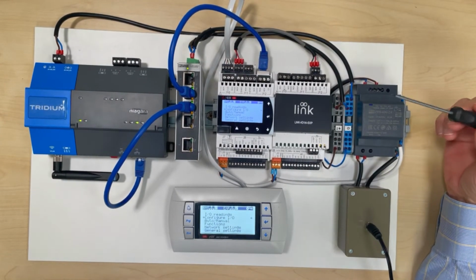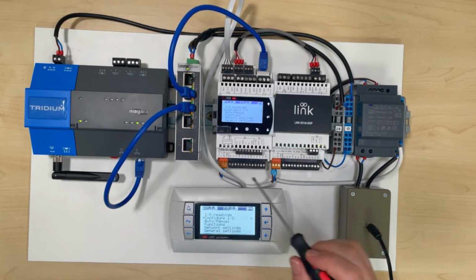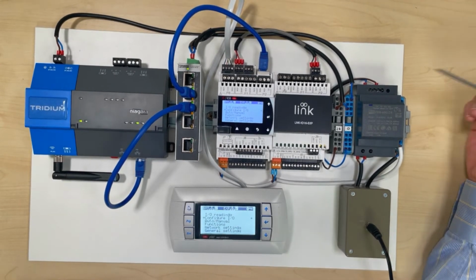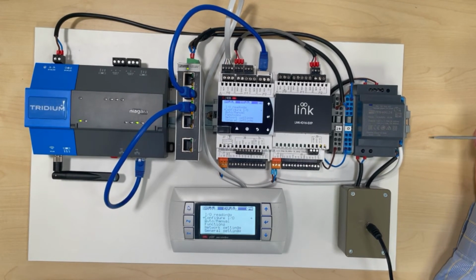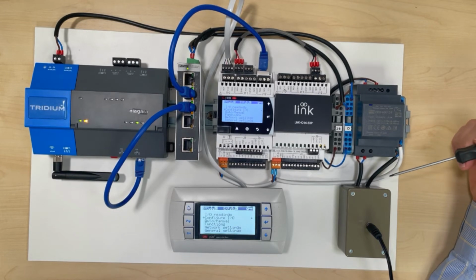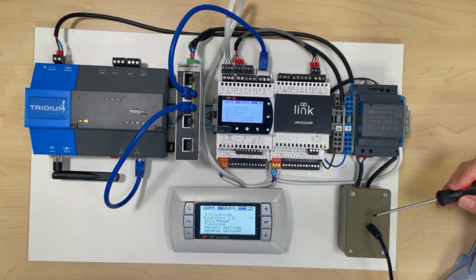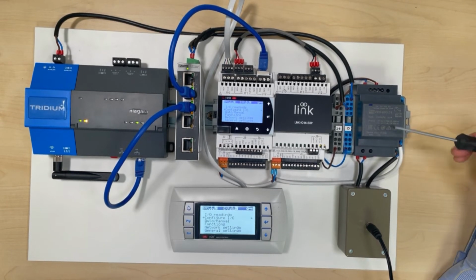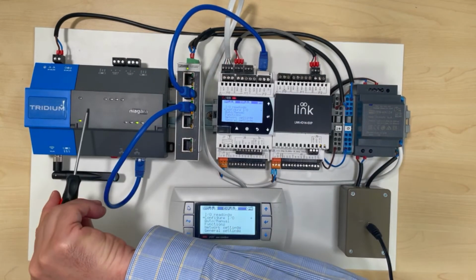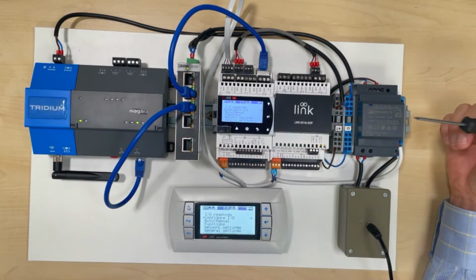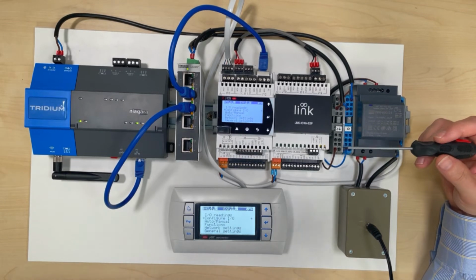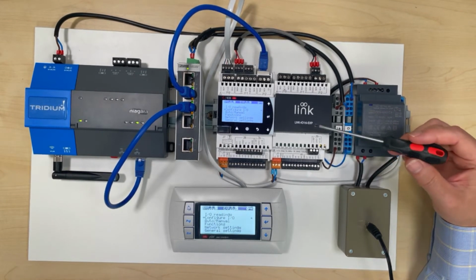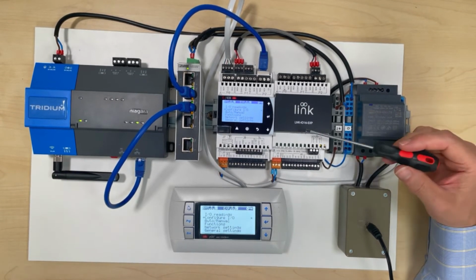Power wise, you've got two options here. You can have 24 volt AC, or as I'm using here, you can have 28 to 36 volt DC. So you've got to be a little bit careful here. What's actually happening on my test rig here is I've got a power brick that's 30 volt. It comes into a converter, and that converter is just providing 24 volt for the JACE. So if you've got things like JACEs and maybe trend controllers using 24 DC, you need to consider a different option for your Link IO system.